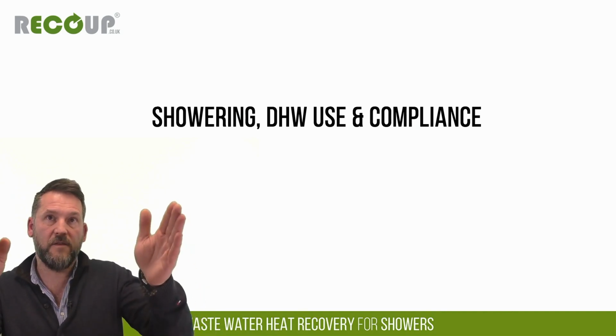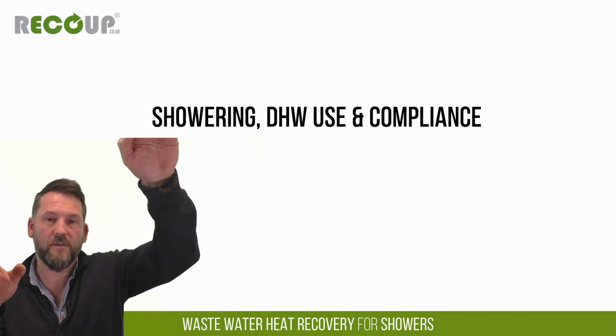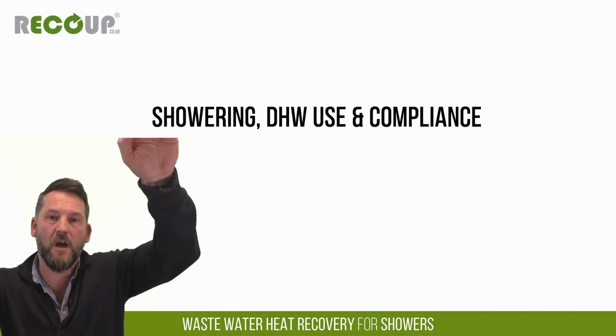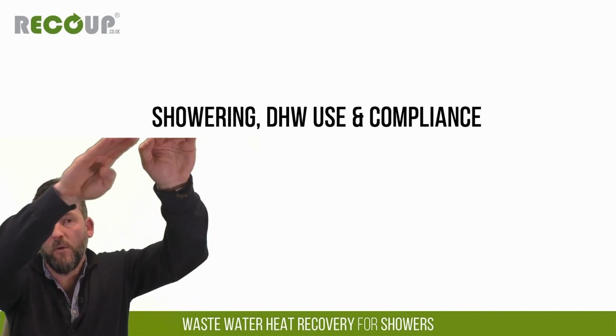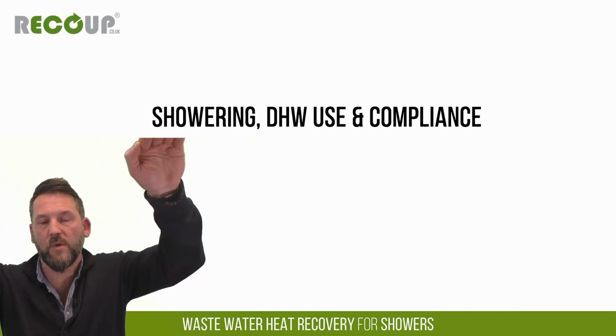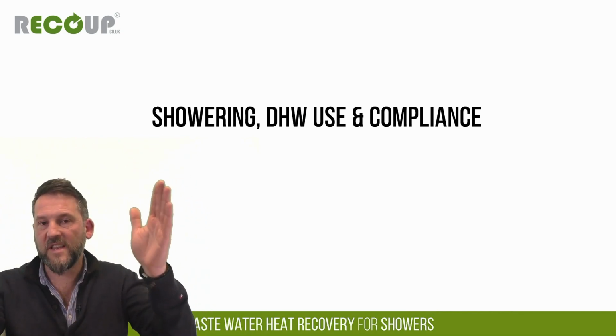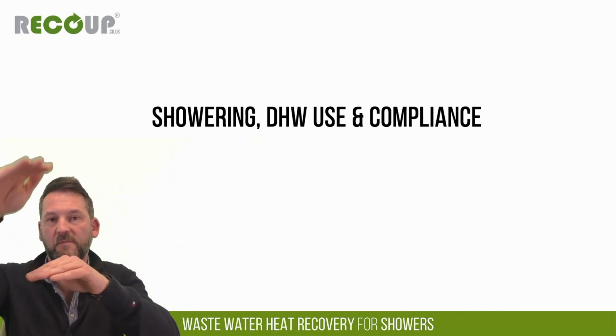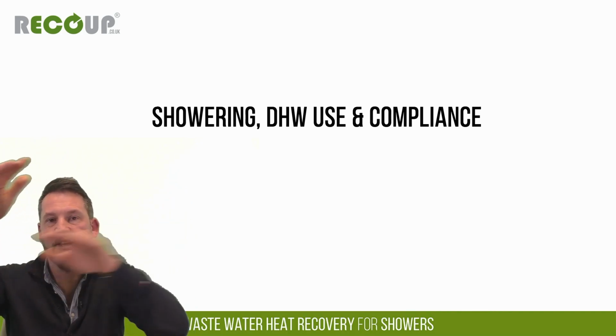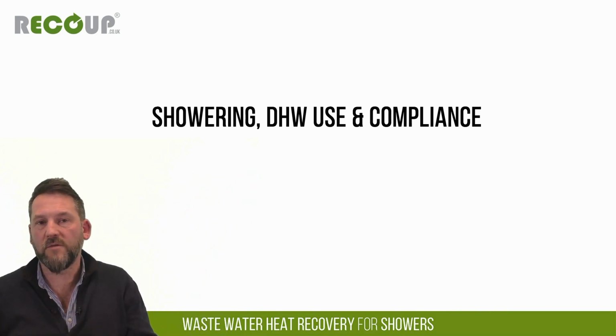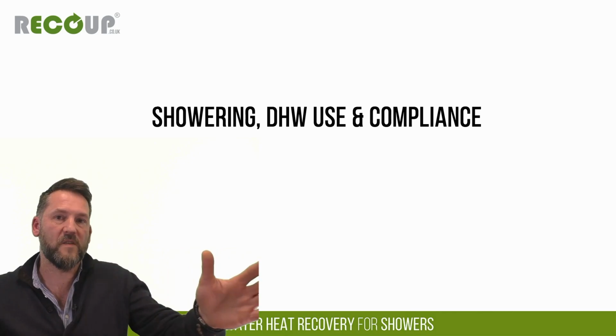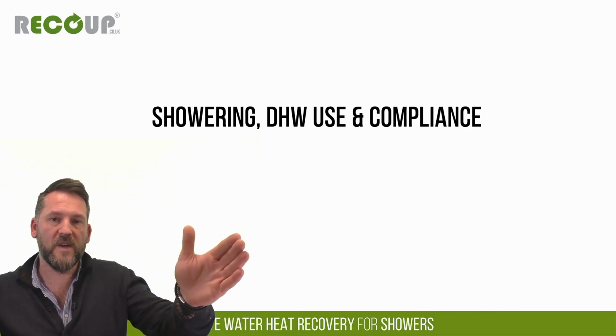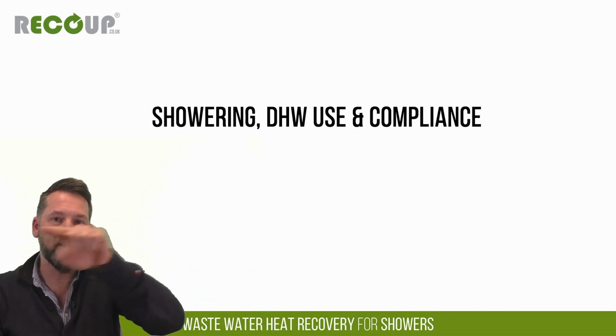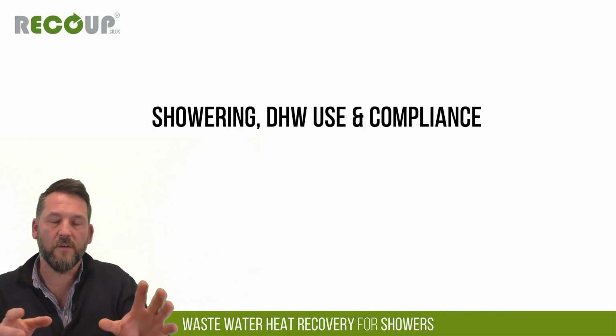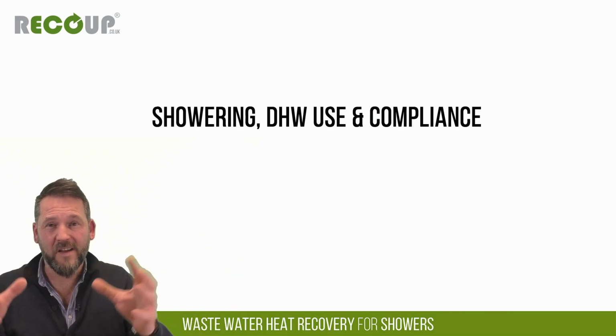In practice, if you have a shower on the first floor and the wastewater heat recovery either just below the ceiling or within the ceiling void, the fall that you need from the shower to the wastewater heat recovery unit, that angle generally dictates that more than 3 meters isn't possible. The height in a ceiling floor void tends to dictate it. So in most scenarios, it's difficult to design with the wastewater heat recovery and the shower further than 3 meters. That also then falls into that 4.75 meter maximum length on the System B pipework. Generally, all that is designed in quite well.